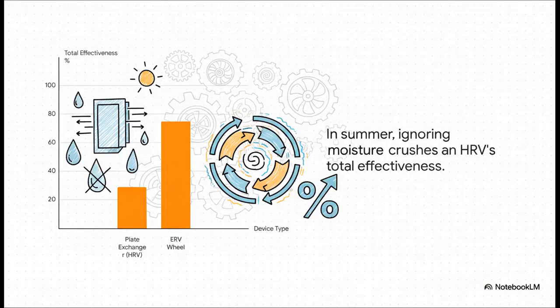And wow, this chart just says it all. Look at this performance gap. In the summer, a simple plate exchanger and HRV might be okay at transferring temperature, but its total effectiveness is only 29% because it completely ignores humidity. The ERV wheel, by managing both, hits a total effectiveness of 75% or even higher. I mean, it is not even a close competition.